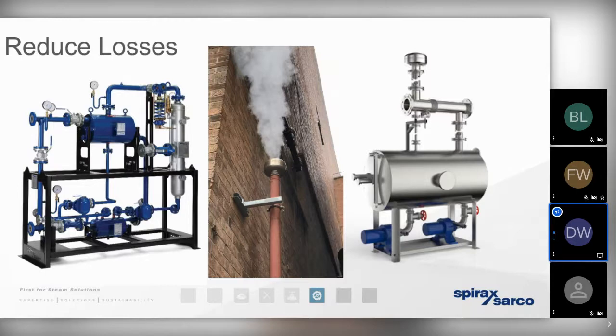So if you look over towards the right-hand side of the screen, we can see an example of an exhaust vent condenser. And by passing that flash steam across a very simple heat exchanger, it means we're condensing a significant mass of that flash steam. We're letting that flash steam expand as it sees atmospheric. But at least if we're recovering some of the heat energy, we're increasing the mass of condensate that we can otherwise return back to the boiler house.